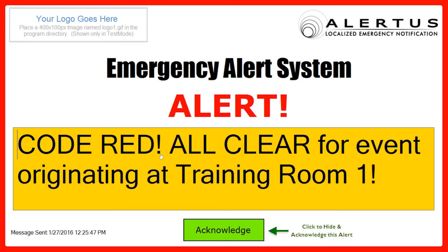All right. And it's done. All right, excellent. Thank you very much, Rodrigo. You're welcome. So a couple of things you saw there was the information that was coming out of the panel. We were able to create an action where we'd set off the Alertus system. It would convert that text string to voice and make that announcement over the speaker system, and then automating the all clear with standard procedures for first responders that come in, investigate the fire, and then clear out the fire panel.